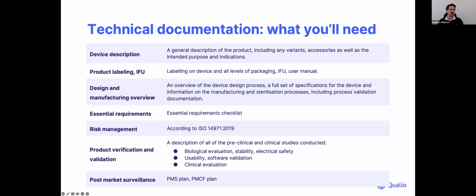Broadly speaking, there are different sources of information for what should be included in a technical file, but we generally find that Annex 2 of the EU MDR and Annex 2 of the IVDR provide quite a good overview of what should be in a technical file. So, while it's not applicable in Great Britain, it's still quite a useful guide for what should be in there. And this structure follows that format as well.